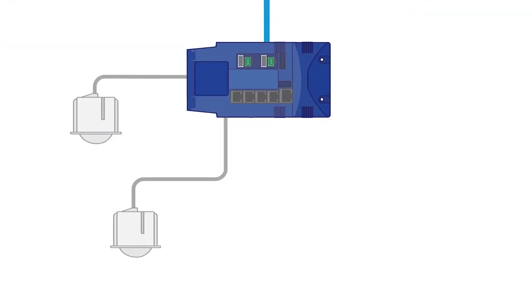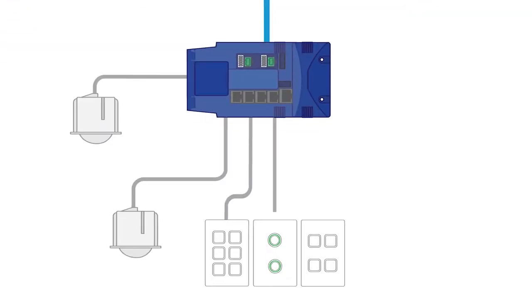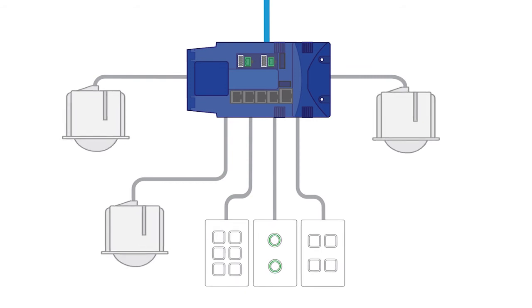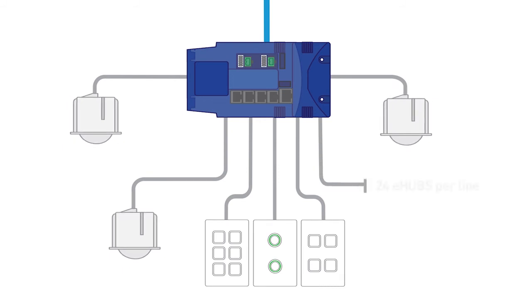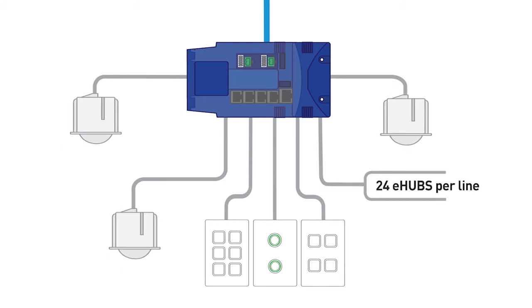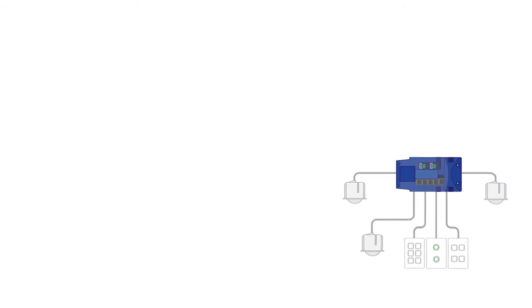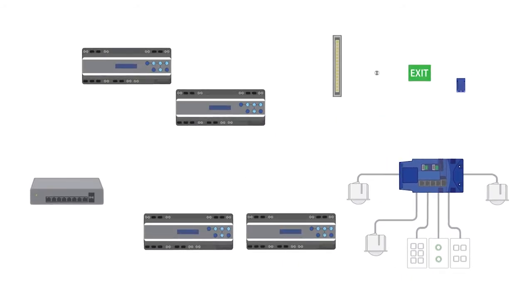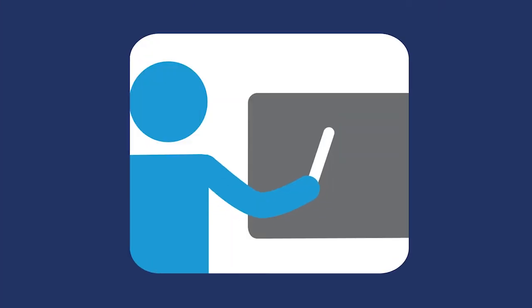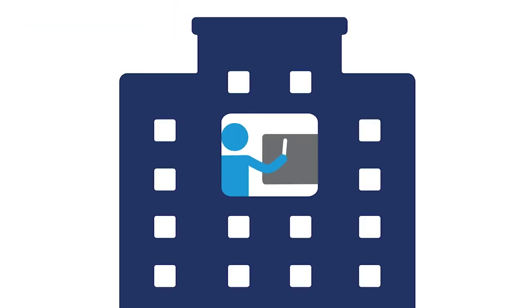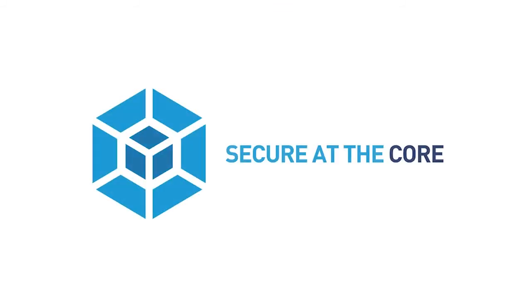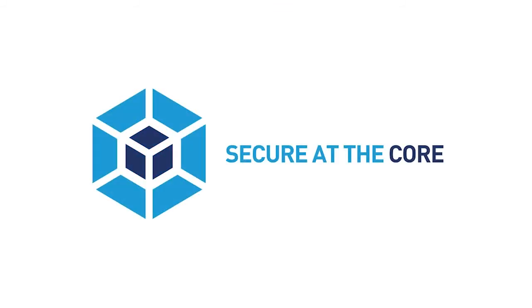These include unique Rapix eHub application controllers that manage power requirements and DALI communication for input devices such as switches and sensors. Up to 24 eHubs can be installed on a DALI line. With this simple overall system architecture and no need for gateways or bridges, the system is easily scalable from single boardrooms to the largest multi-storey buildings.